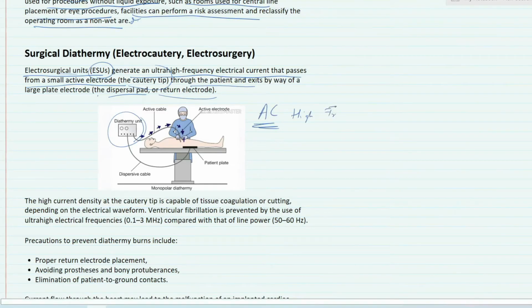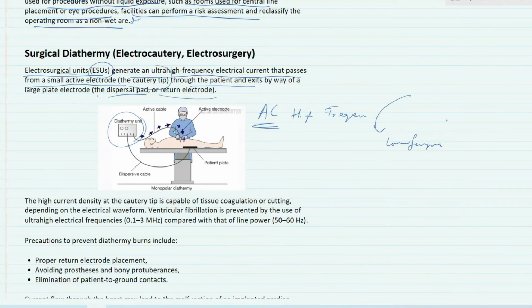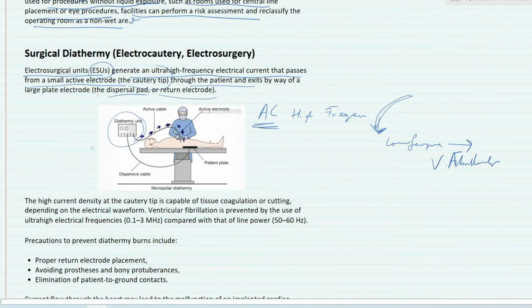This is very important to understand, because if by some fault it turns into a low frequency, which it very rarely does, there are certain case reports, two of which I have read, it has the potential to cause what? Ventricular fibrillation, right? So this is very high frequency, and here is the tip, and then high intensity, high frequency current passes through the patient plate that we all apply to the patient, and then from there the circuit is complete.